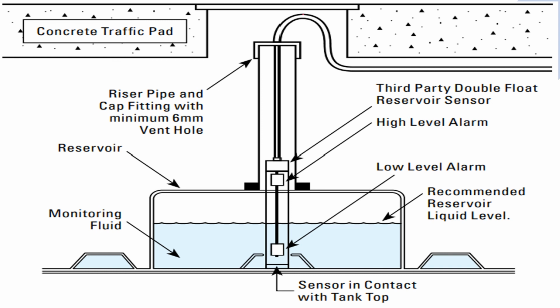It doesn't happen much with the newer tanks. I've seen these at older tank systems. So just be aware if a contractor or technician tells you they just had to remove a little bit of brine solution, that may be what they're having to do it for. It could become a seasonal thing. You may have to replace all the fluid out of your reservoir and replace it with the manufacturer's recommended liquid so that it won't fluctuate as much.